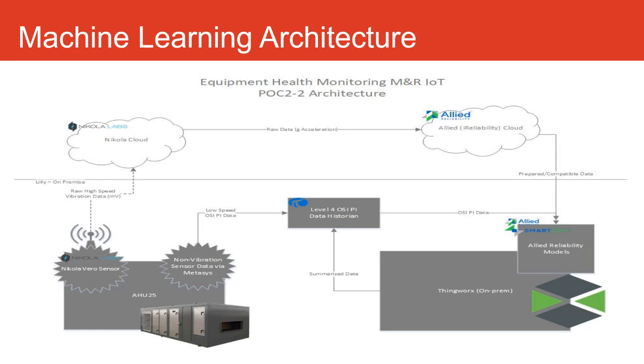Here's a pictorial of what I was talking about earlier with these POCs. On the left-hand side you see the air handler with the Nikola Vero sensor sending vibration data up to the Nikola cloud. We also have a Metasys system that's non-vibration - temperature, humidity, flow, pressure, damper percentage - stored via Metasys going into our level 4 Pi Historian. What I'm trying to do is mash the vibration and temperature data from the top left into the Reliability Cloud from Allied Smart CBM, bring that into their Allied Reliability failure mode models in Thingworx, and bring the process data from OSI Pi down into Thingworx as well - now I have the mashup between the process data and the vibration data.